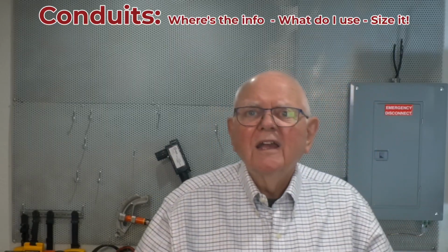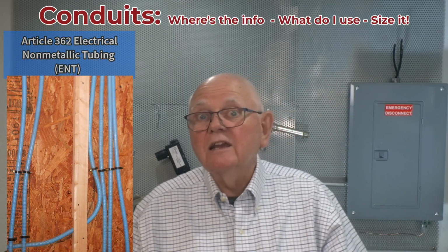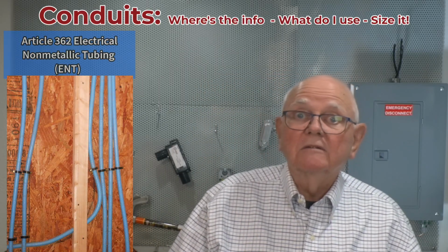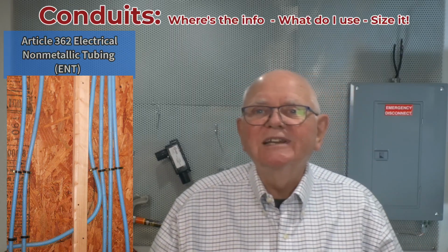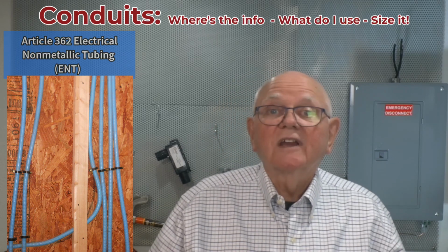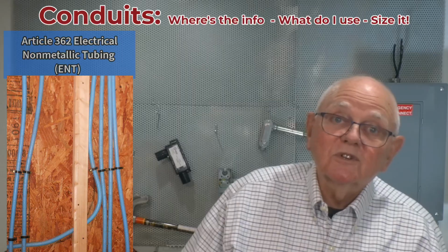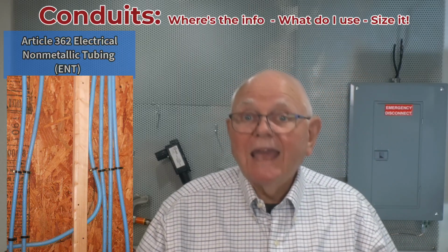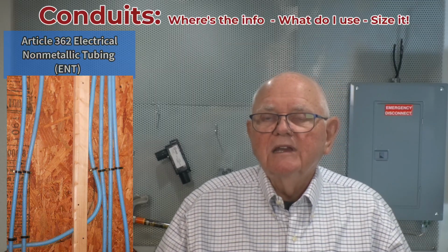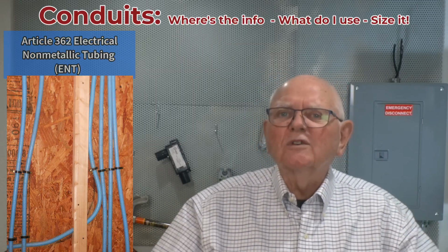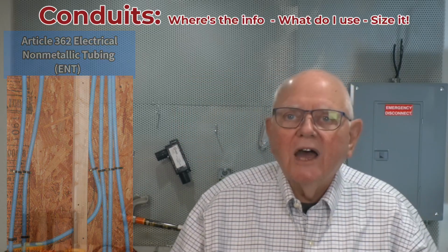And then we have electrical non-metallic tubing. So we just looked at electrical metallic. We have electrical non-metallic tubing. Article 100 tells me that this is non-metallic, by definition. It's pliable. It's a corrugated raceway, and it's resistant to moisture and chemical atmospheres, and it's flame retardant. And it can be bent by hand. That's what it means by pliable. It says without undue force, I'm able to bend this with my hand. So anyway, that's electrical non-metallic conduit.